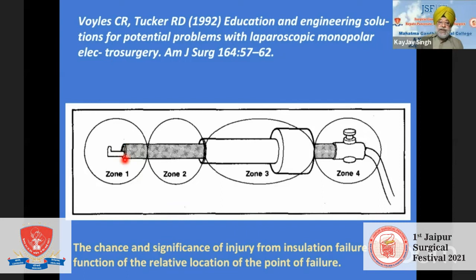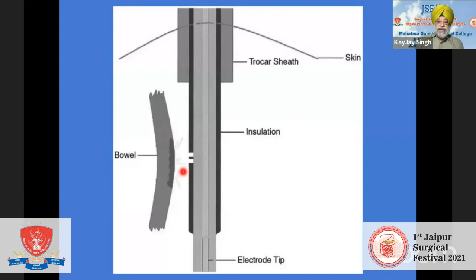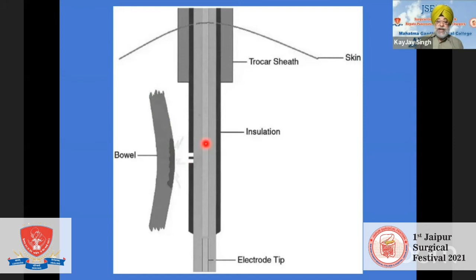The authors concluded that the chance and significance of injury from insulation failure are a function of the relative location of the point of failure. So it depends on which point it is failing. If it fails at this point, chances are that the surgeon will avoid any injury. But in these areas, it can cause havoc. This is the graphic depiction of insulation failure. You see, this is the break in the sheath, with any bowel coming here or in the vicinity also. If the cautery is in the spray mode, it'll leak from here and cause a disaster. And if it's a direct contact, then there's a guarantee that something is going to go wrong.